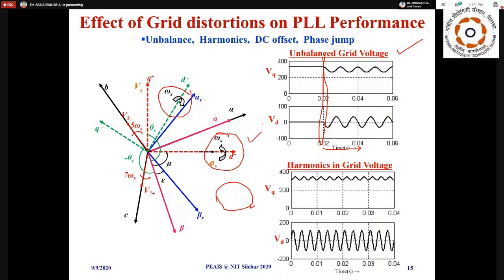We can see two frames here: Q plus is the positive frame and Q minus is the other frame. They are apart at an angular displacement of 2 theta. This 2 theta leads to all kinds of oscillations: oscillations in the voltage, the power, torque, speed, etc. Whatever we assumed earlier for the PLL is that VD is 0, but VD is not 0 under unbalance. Similarly, under harmonics in the grid voltage, you have harmonic frequency components.